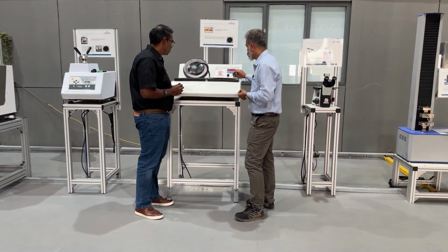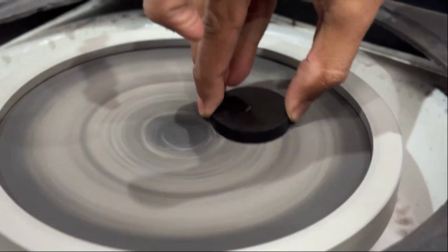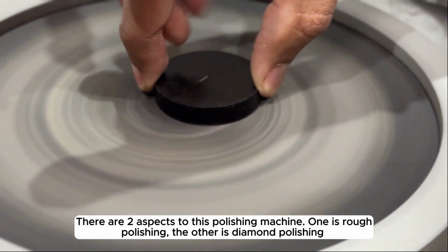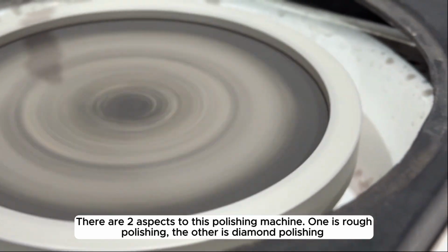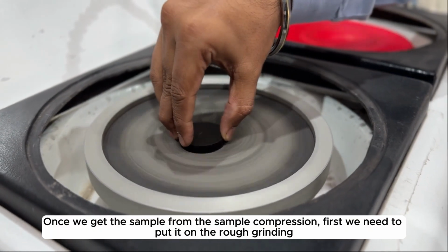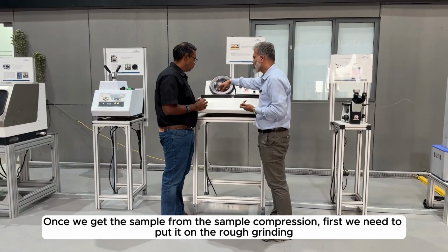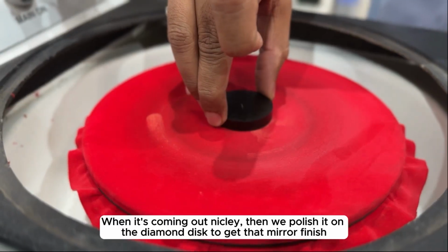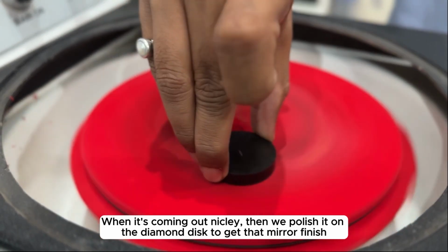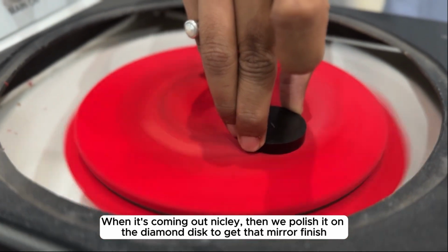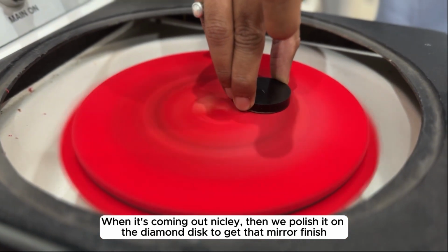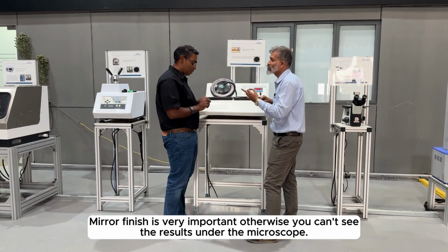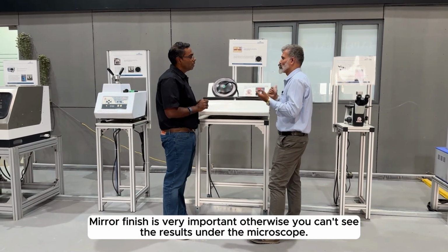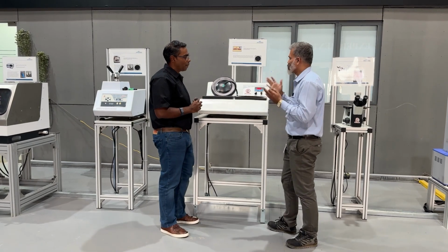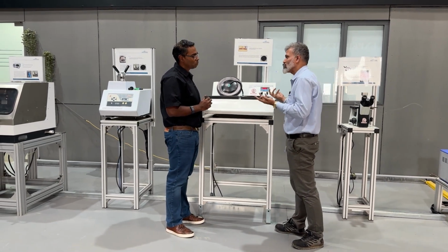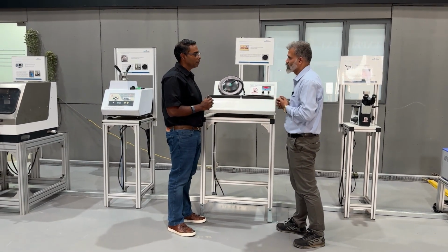Correct. For this polishing machine there are two aspects. One is rough polishing, after that diamond polish. Once we get the sample from the sample preparation, first we take it to this rough grinding. And when you see that it's coming out nicely, then afterwards we put diamond paste over here and polish it till the mirror finish is achieved. Oh, mirror finish. So mirror finish is very important, otherwise you cannot see it in the microscope, because we are looking at 0.2, 0.3 mm. So it has to be mirror finish first.